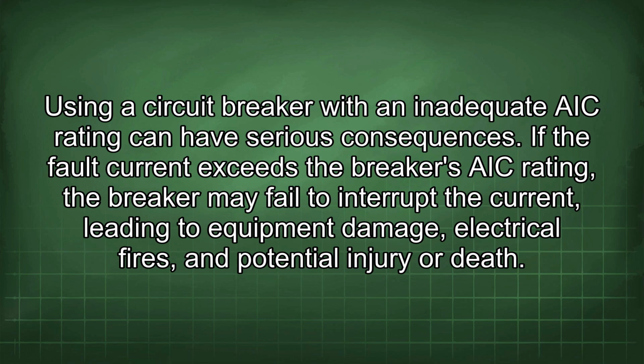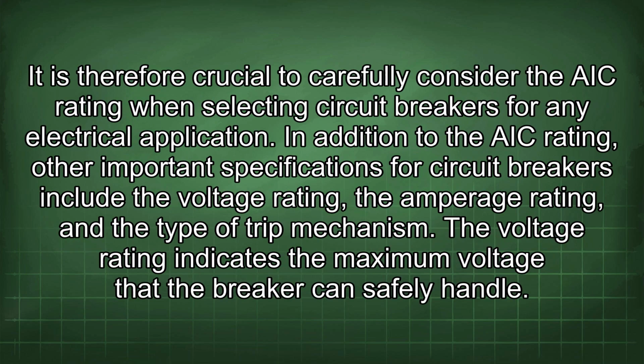Using a circuit breaker with an inadequate AIC rating can have serious consequences. If the fault current exceeds the breaker's AIC rating, the breaker may fail to interrupt the current, leading to equipment damage, electrical fires, and potential injury or death. It is therefore crucial to carefully consider the AIC rating when selecting circuit breakers for any electrical application. In addition to the AIC rating, other important specifications for circuit breakers include the voltage rating, the amperage rating, and the type of trip mechanism.